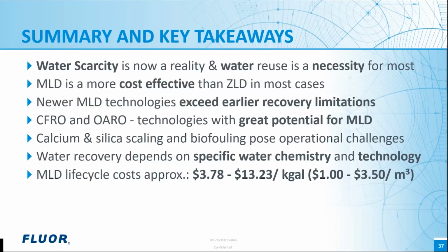The amount of water recovery from liquid waste streams is primarily dependent on site-specific water chemistry and the type of technology considered. MLD is an effective strategy to implement sustainable water reuse with life cycle costs in the range of $3.78 to $13 per thousand gallons, equivalent to $1 to $3.50 per cubic meter.